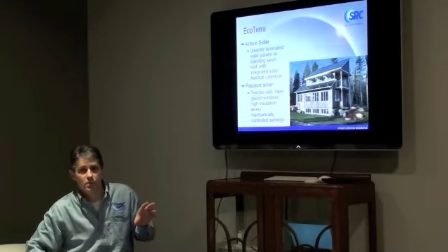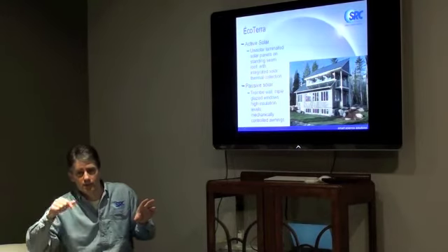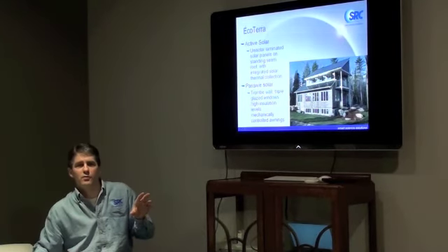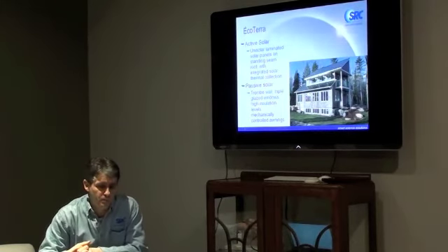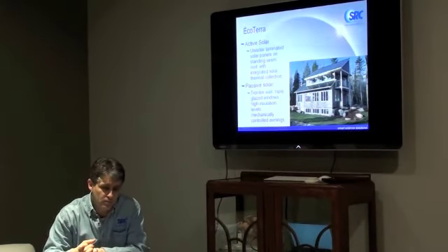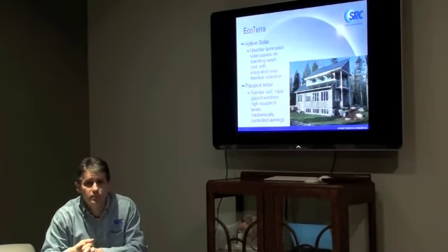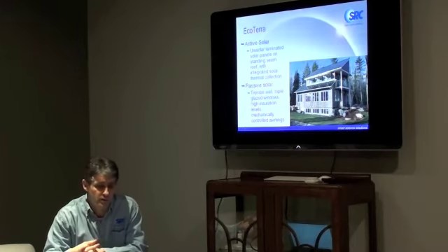The basement floor is hollow core. So they heat the basement floor with the air that they recover off the underside of the panels. It doesn't run as much as they were hoping it would. Not quite as effective as they were hoping it would be.